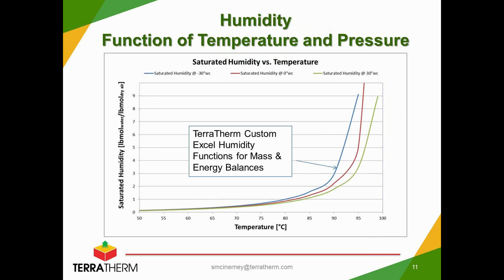Briefly, this is a curve showing that the amount of water in a vapor stream is not only a function of the temperature, but also the pressure of the gas stream, where our operating conditions may range anywhere from, say, at the well field to the suction setup or blowers at 30 inches of water column vacuum, up to a practical limit of, say, a positive 30 inches of water column pressure. You can see in this chart that the moisture carrying capability of those vapor streams under various pressures does change, and it's something that we keep track of. We've got functions built into our Excel mass and energy balance models that look at that carefully throughout our treatment process.